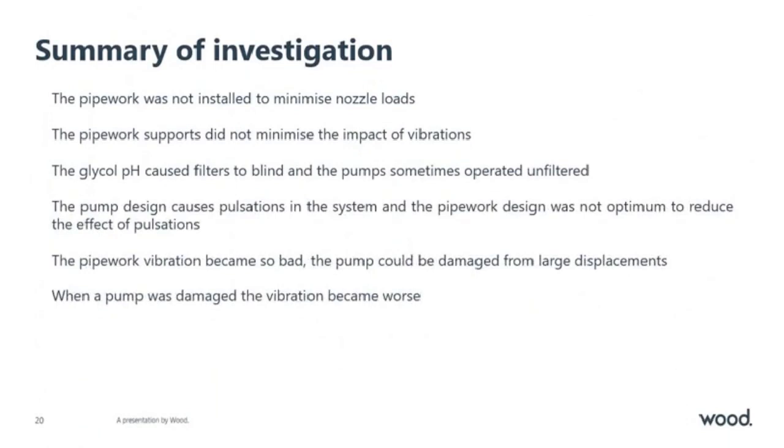So the pipework was not installed to minimize nozzle loads. The pipework supports did not minimize the impact of vibrations. And the glycol pH caused filters to blind more often, and the pump sometimes operated unfiltered. The pump design caused pulsations in the system, and the pipework design wasn't optimum to reduce the effect of those pulsations. The pipework vibration became so bad, the pump could be damaged from large displacements. And when the pump was damaged, the vibration became worse.